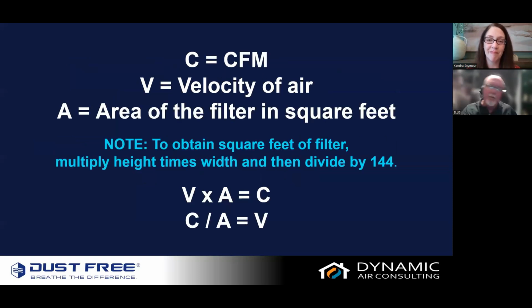So we're going to get a little geeky here. Q equals CFM, V equals velocity, A equals the net free area in square feet. If we have two of these measurements, we can get the third. First of all, to obtain the net free area, we take the height times width and divide it by 144. We also have to remember that filters have a cardboard frame. We need to measure the inside of the frame and not the outside to get an accurate number. If we take velocity times area, that will equal the cubic feet per minute that filter can handle. If we've got cubic feet per minute and we divide it by the net free area, that will give us the velocity that filter can handle.